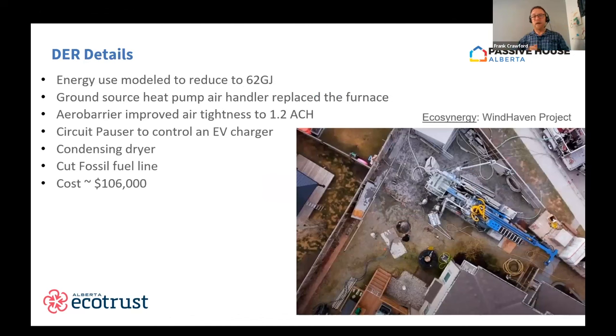So they did what they call the no demolition type of deep energy retrofit. So the only envelope upgrade was to use the Aerobarrier aerosolized caulking system to improve the air tightness. They brought it down to about 1.2. And they installed a ground source heat pump. So this involved that large piece of equipment you see in the photo there, drilling three vertical bore holes on their property that goes back to a larger ground source heat pump. And then they again fully electrified their building, cut the fossil fuel line.